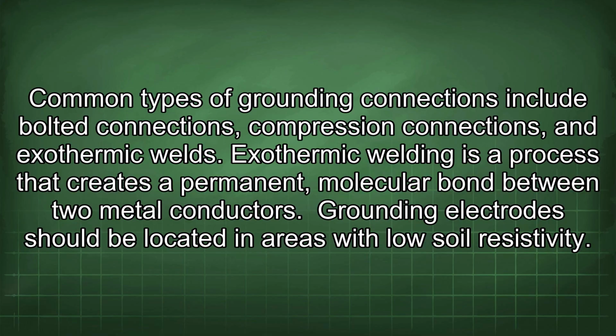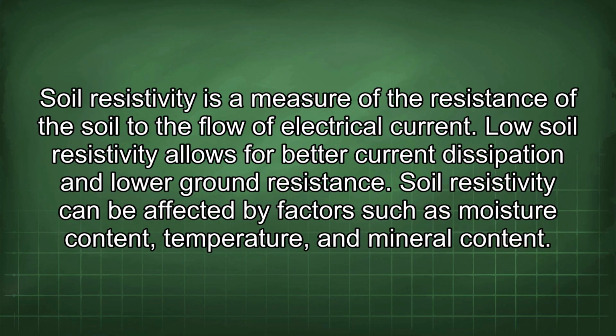Grounding electrodes should be located in areas with low soil resistivity. Soil resistivity is a measure of the resistance of the soil to the flow of electrical current. Low soil resistivity allows for better current dissipation and lower ground resistance. Soil resistivity can be affected by factors such as moisture content, temperature, and mineral content.